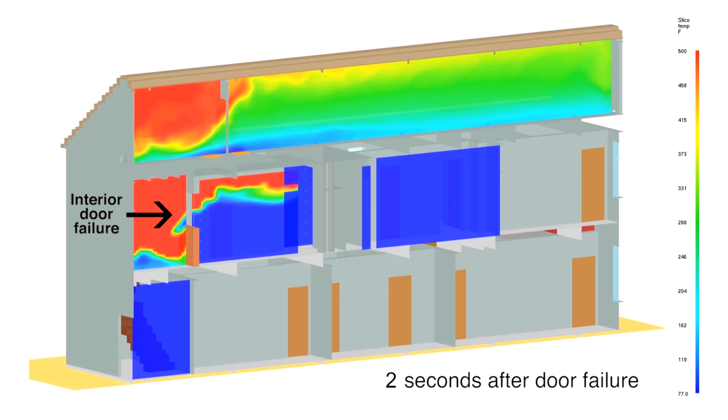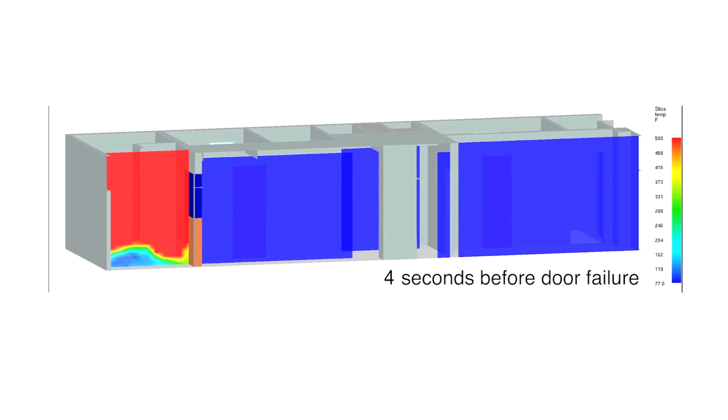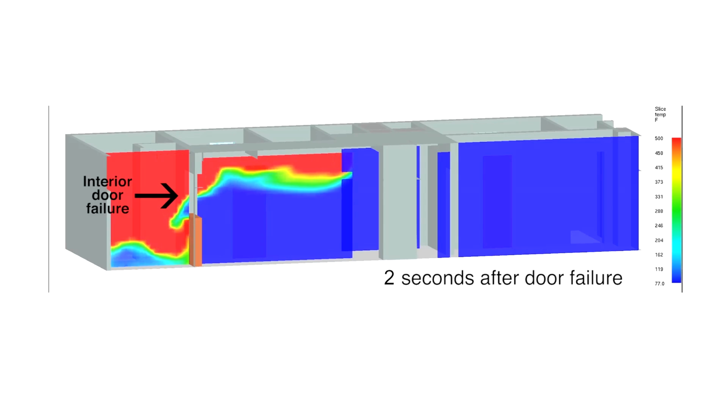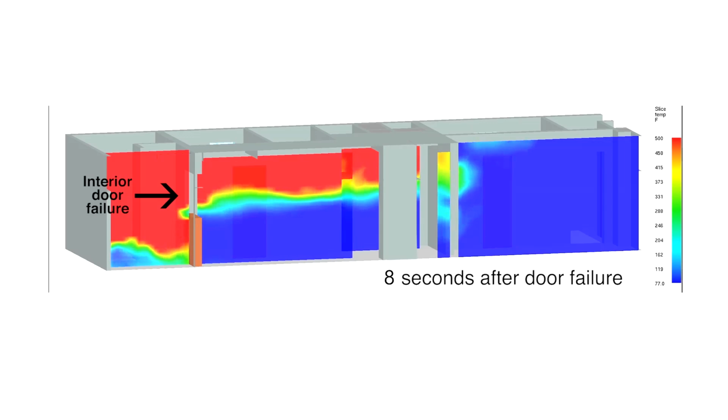The spread of fire and hot gases into the second floor of the structure was initially stopped by a closed, steel-faced wood frame door. After exposure to elevated temperatures and pressure from the fire in the porch area, the wood frame of the door decomposed and the upper portion of the door collapsed, allowing the higher pressure hot gases to flow into the lower pressure hallway where the captain was located.